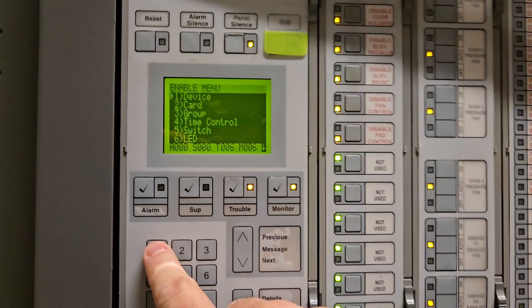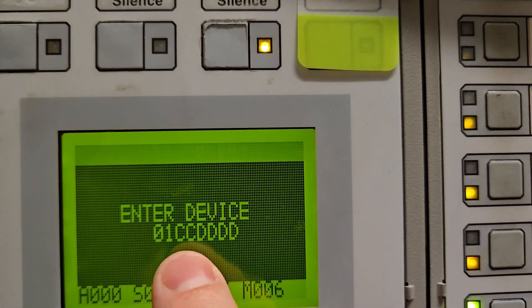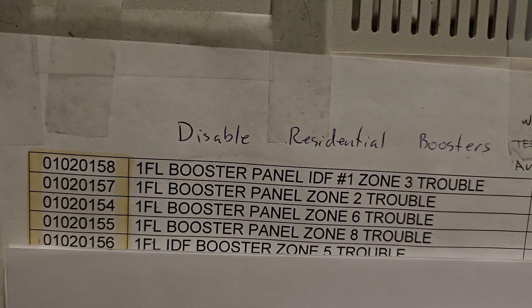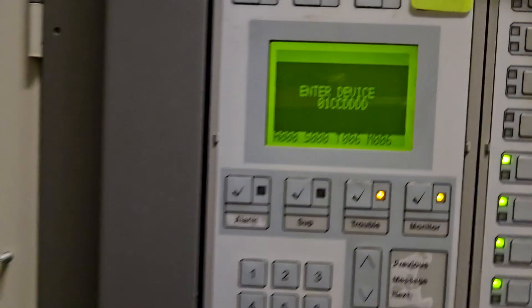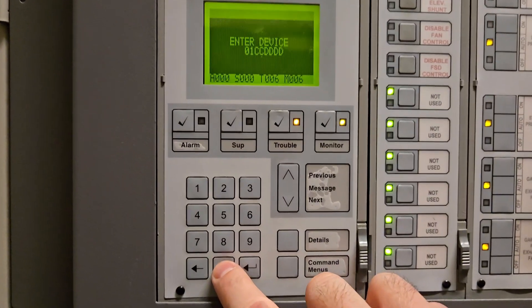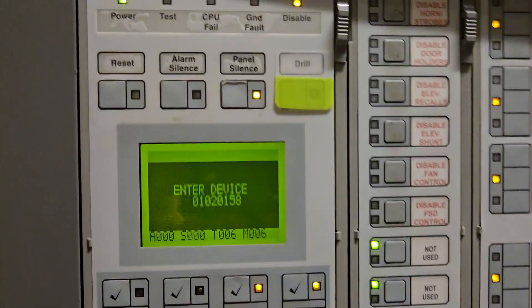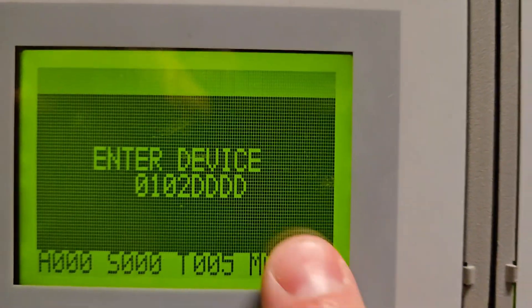I'll hit number two, get the next menu, and hit number one for device. Now I'm in the enable menu. I'll follow the exact same process in reverse to re-enable all these points. I still have zero one for the panel, CC for card, and the four D's for device. Starting with 01-02-0158 — the first floor booster. I put in zero one zero two, zero one five eight, check my number, and hit enter. My trouble count goes from T6 down to T5 — one less trouble.